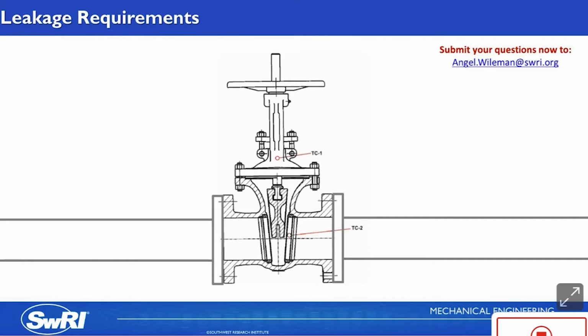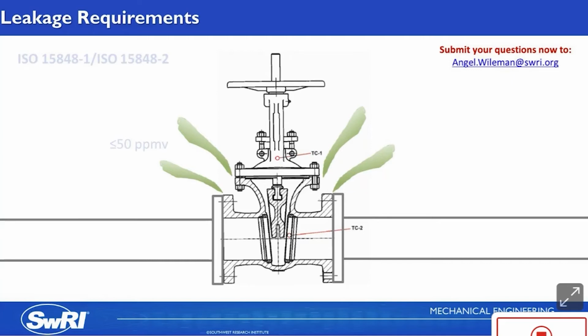So we've discussed pressure and temperature instrumentation, but now I'm going to switch gears to perhaps the most critical measurement, which is external leakage. First, let's discuss external leakage requirements defined by the standards, and then we'll talk about the methods for how to measure them. For ISO 15848-1 and -2, the allowable leakage from body seals is 50 parts per million by volume. This max allowable does not include leakage from the end flanges, but it's good practice to measure this leakage so it doesn't affect other readings.